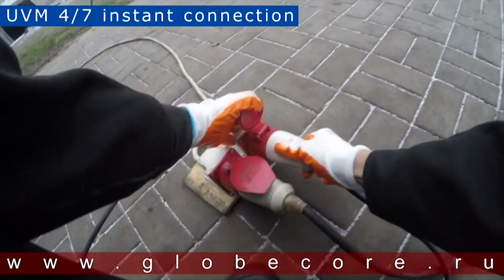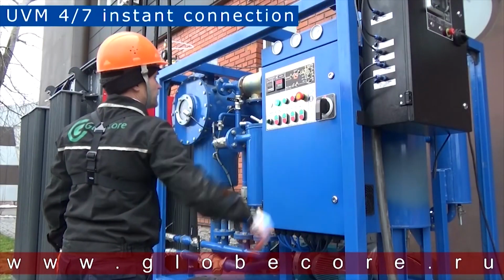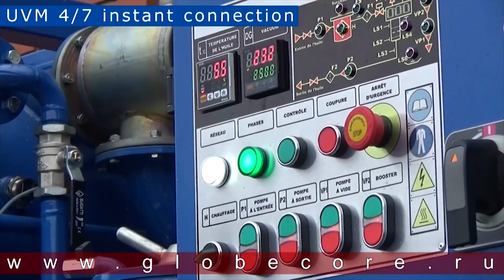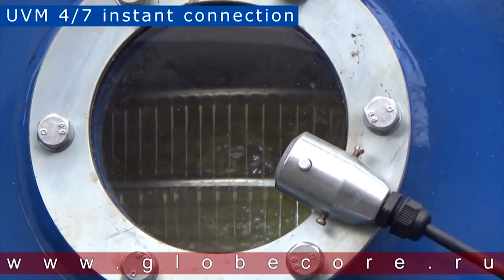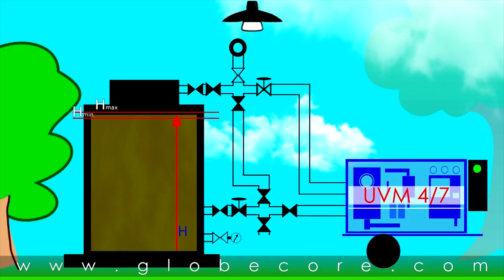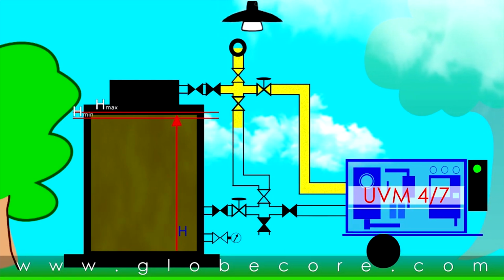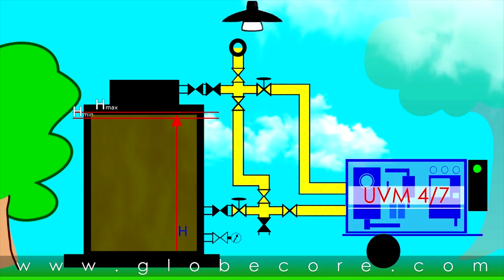The TSS system is powered up. From the control panel, the limits of the TSS operation are set. TSS is activated. The electromagnetic valves on the crosspieces open. Oil processing commences through the bypass line. The pipes are filled with oil, releasing air.